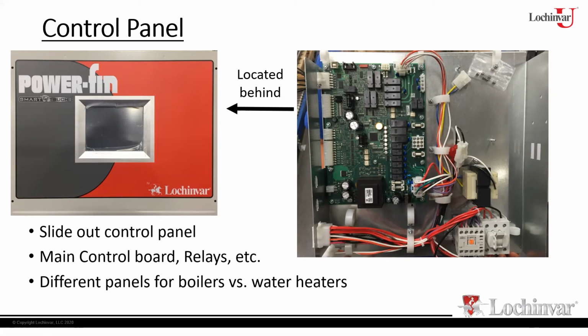Now, depending on whether it's a boiler or a water heater, you may have a couple extra pump relays for a boiler, but again, not much. Nice thing about this, your control module is the same control module across the board. Whether we're talking from 500,000 to 5 million, it is the same board. How we can get by with that is that the program for every configuration is built into the control module.